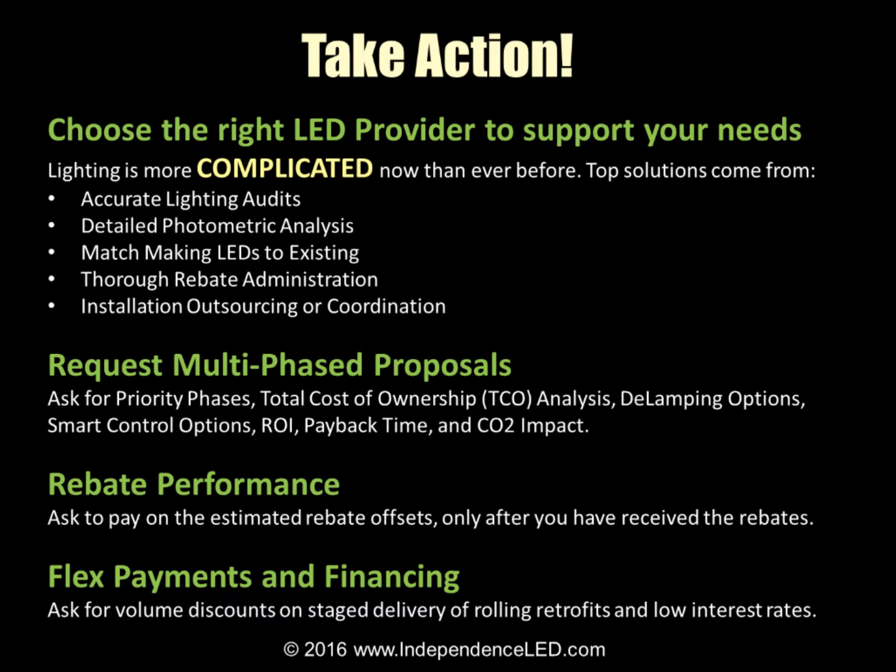Rebate performance I talked about, and how important it is with the offset and really being intelligent, because sometimes changing a linear module like a fluorescent tube has less of an advantage, like a $5 rebate versus a $50 rebate by changing the whole fixture. Well, we did that in one of the Burger King cases where there was nothing wrong with the housing. So it killed me to take, in effect, a working housing for a fixture, which mathematically would have made sense to keep from a labor standpoint and put in the new LED modules over fluorescent tubes, but because there was a $50 rebate for the new fixture, that brought the fixture cost down to under the cost of the 4 fluorescent module replacements, and now somewhere in a landfill in New Jersey, there is a metal housing for many troffers.